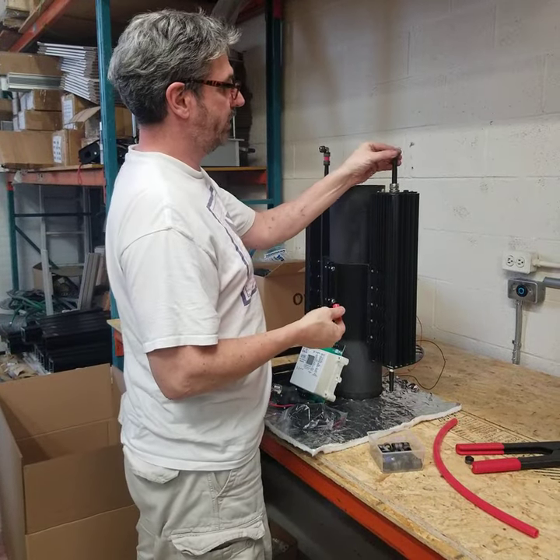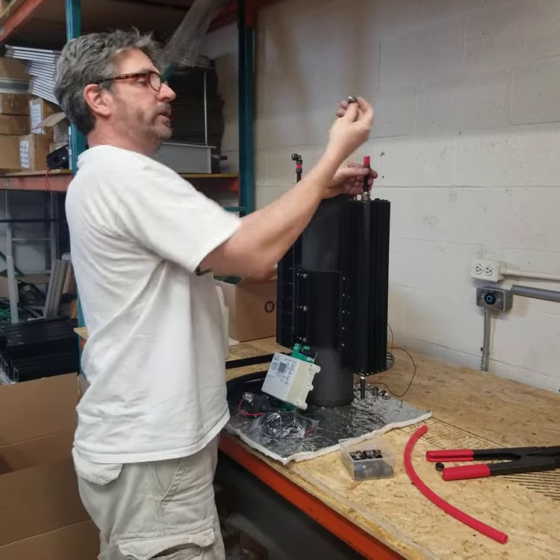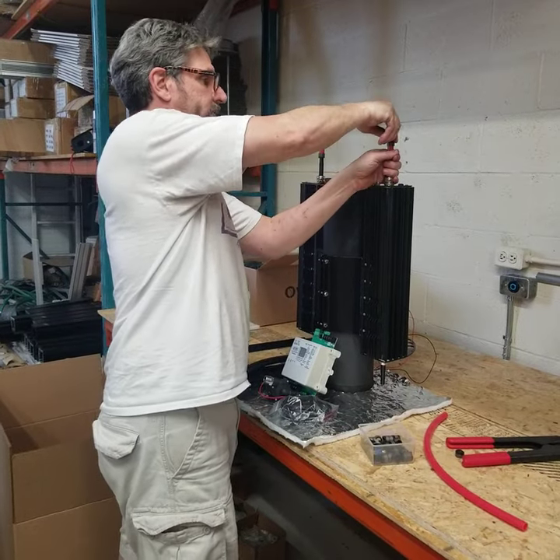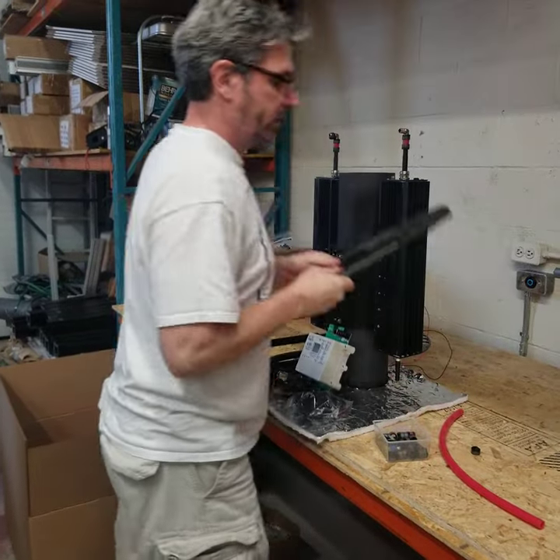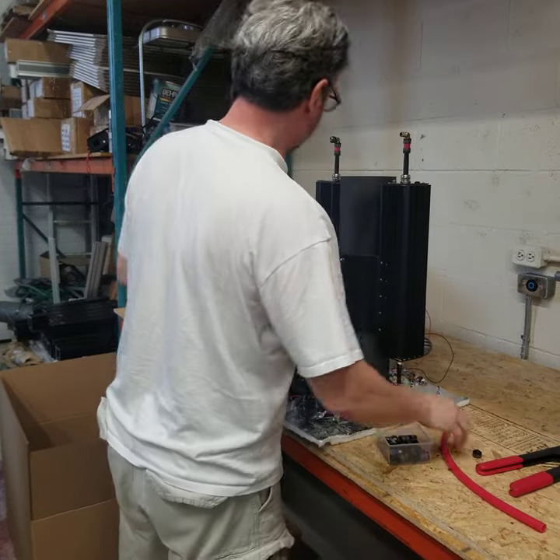Your ring goes on our pre-machined PEX fitting top — we drop it on. We have a second ring on our PEX fitting that goes on top. We close it down. Make sure they're nice and taut. We use our clamp to clamp the PEX on. Make sure it's nice and sturdy.